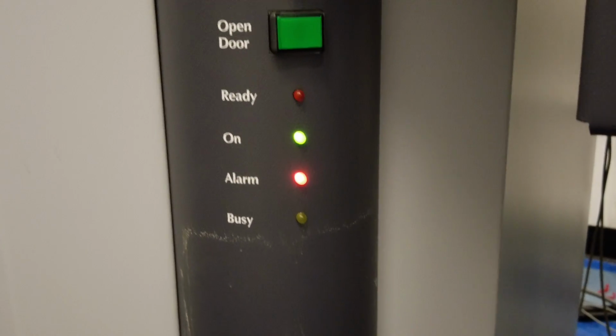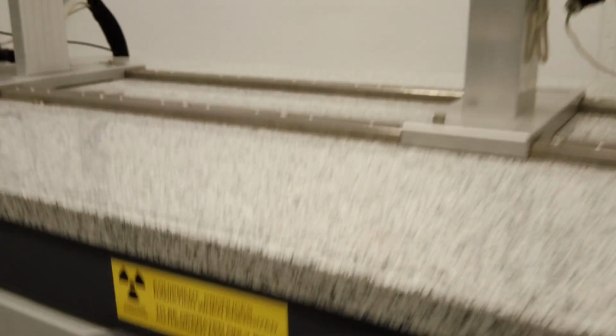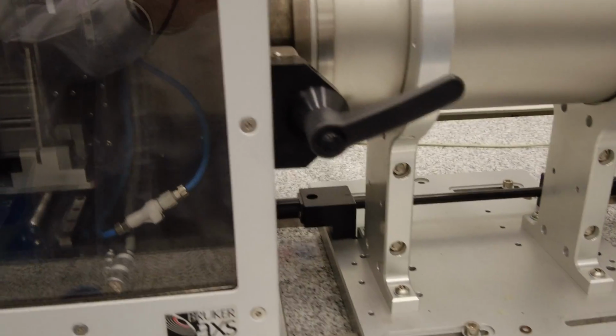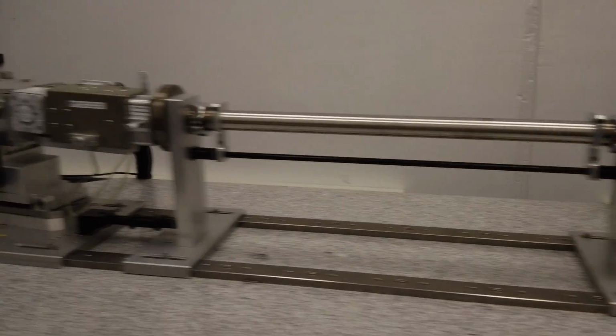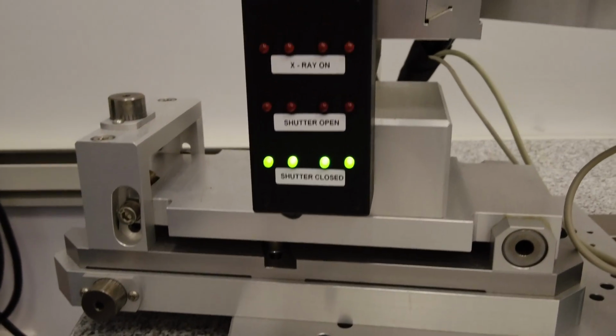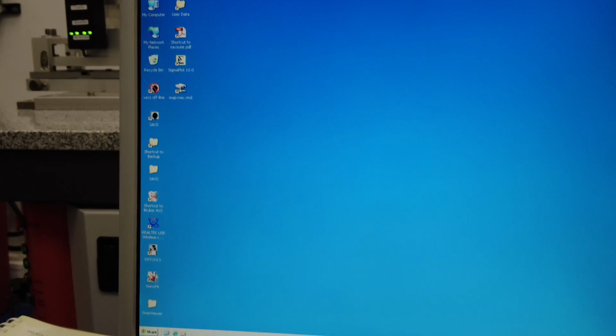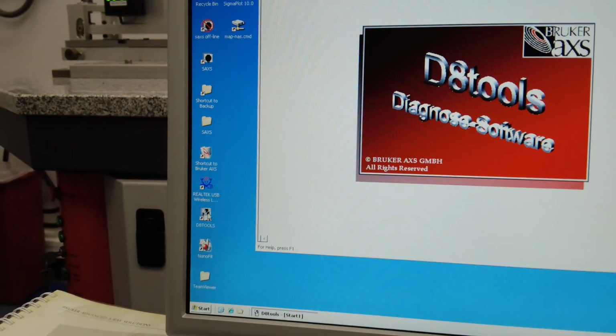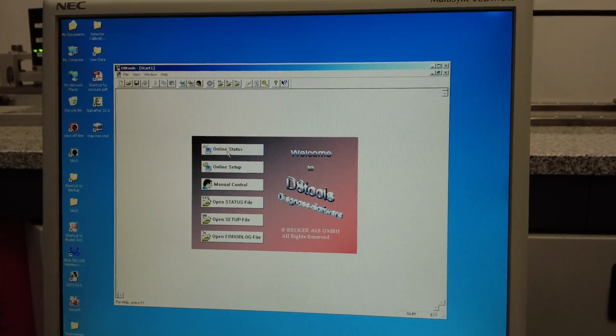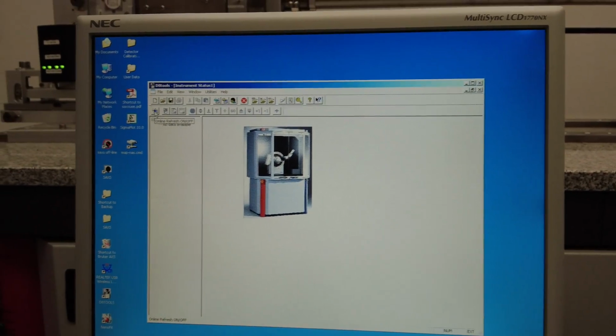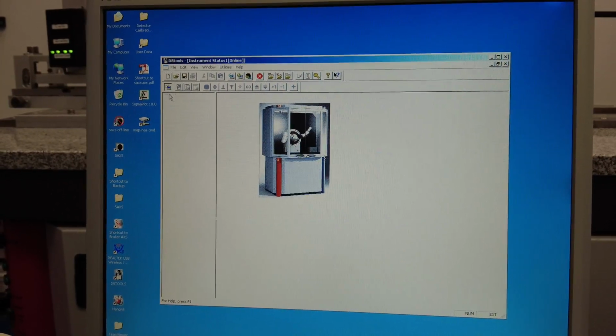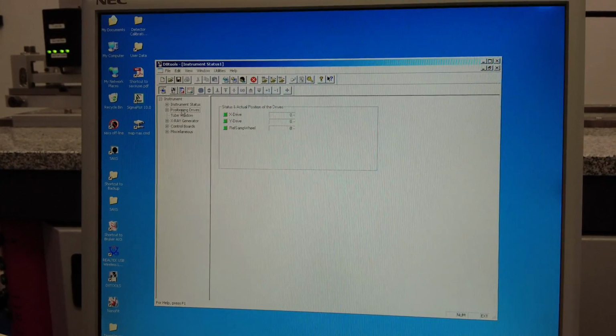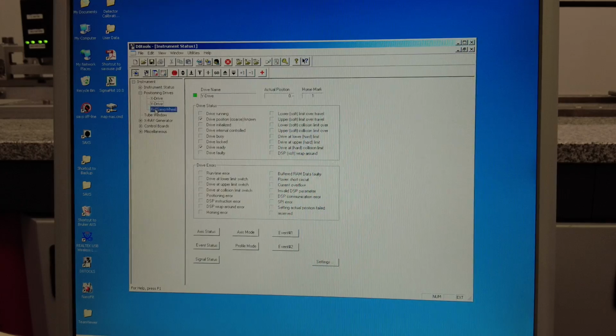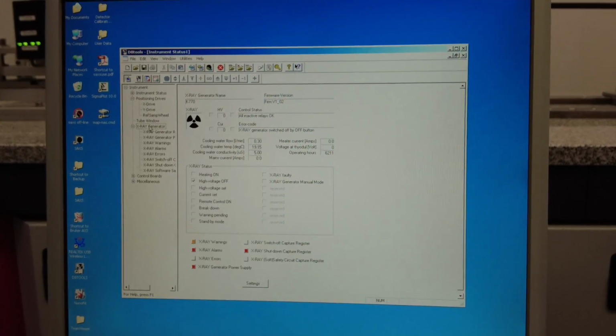Now you can see that the alarm light is turned on. I did hear the relay click over here, so probably this relay here. And I have the shutter that's closed. Let me open the D8tools. Over here, online status, connect. X, Y, ramp, this is okay. Shutter is closed. X-ray generator.